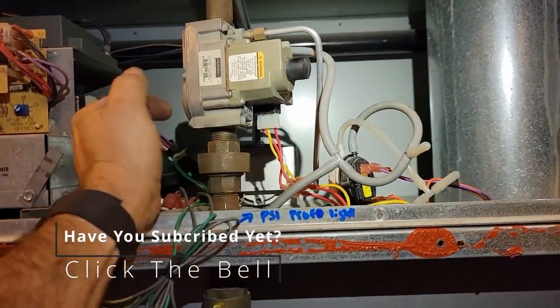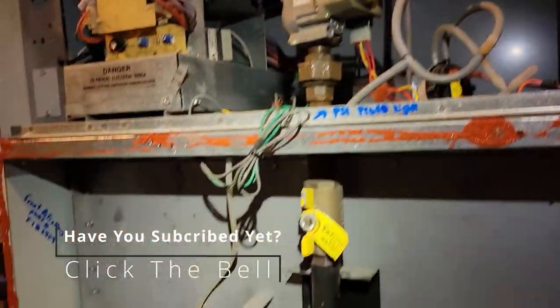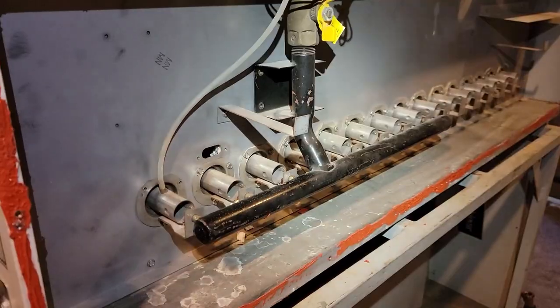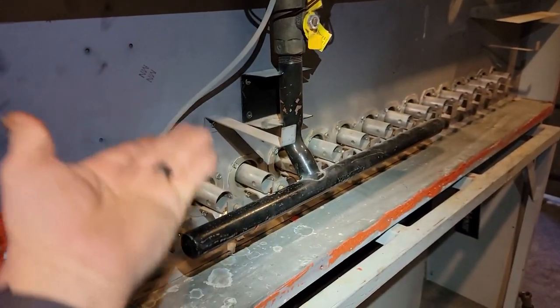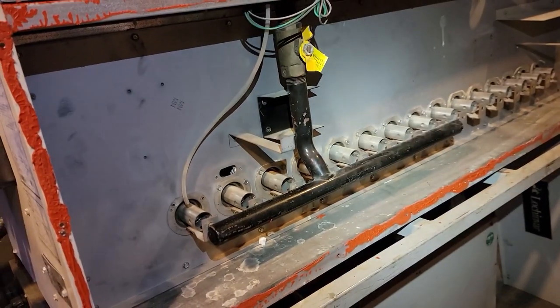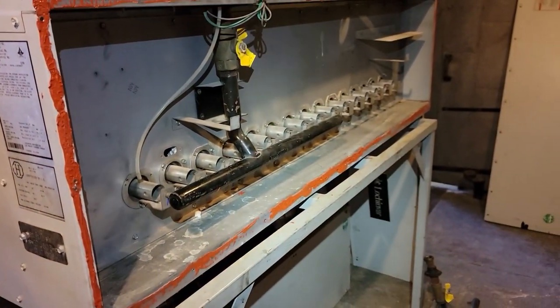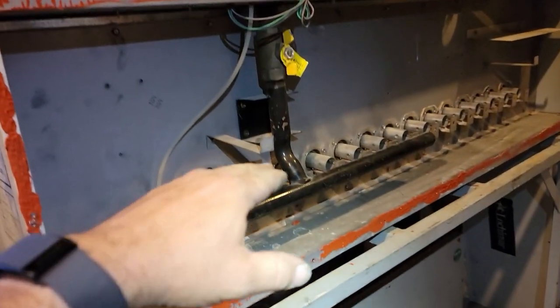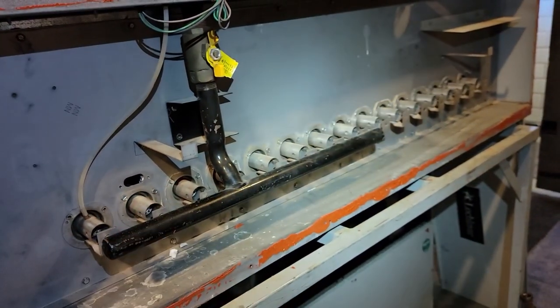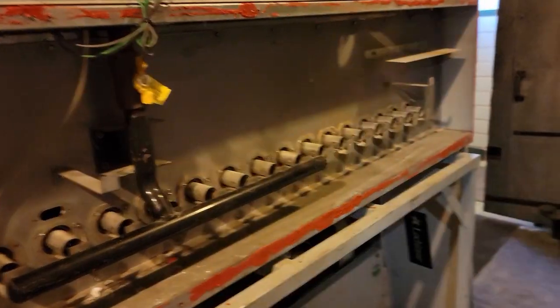I ended up going through, pulling out these first four or five burners here, making sure there's nothing causing disturbance. Got everything back together, talked to the factory, got the gas pressure set right. Trying out the new Testo 300 and CO is 800 parts per million.